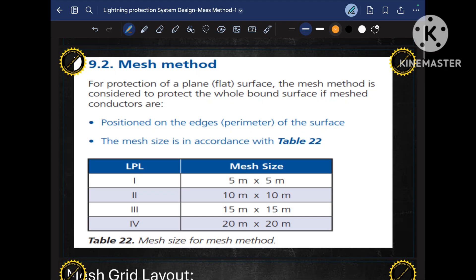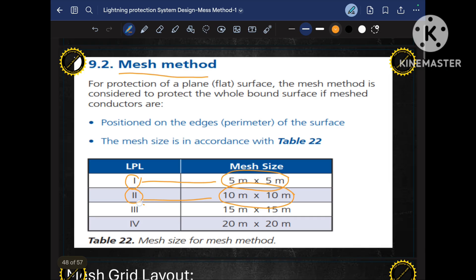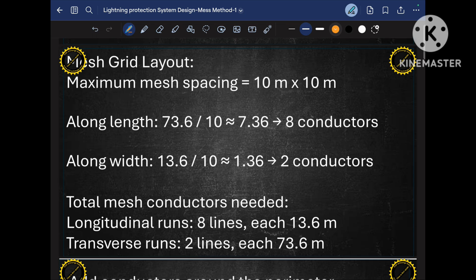As I mentioned when discussing the three different methods in part 2 or part 3, for different classes of protection there is a different rolling sphere radius, different protection angle, and a different MESH size. As per IEC standard: class 1 requires MESH size 5m x 5m, class 2 requires 10m x 10m, class 3 requires 15m x 15m, and class 4 requires 20m x 20m. Since our class of protection is class 2, our MESH size will be 10m x 10m.